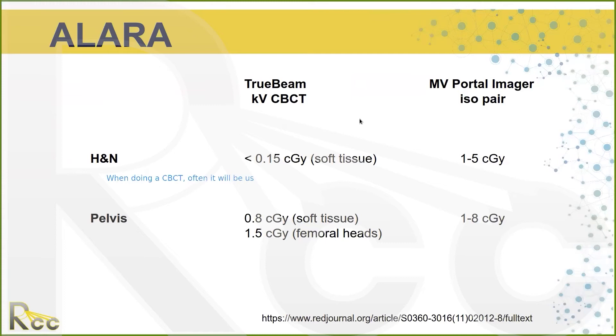There are settings you'll learn about when you use cone beams — you can actually adjust the dose the patient receives by choosing different settings. That's something to discuss with your team. Usually more dose to the patient means you get more information. You can get a wider field of view and see more anatomy, but the trade-off is a little more dose and it takes a little longer to complete the cone beam.